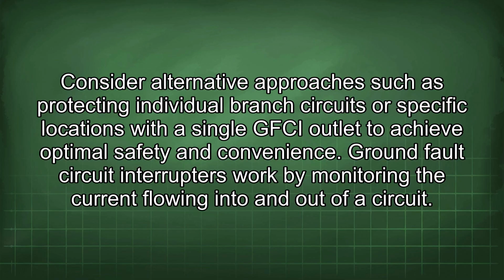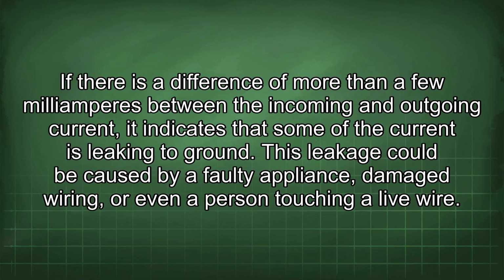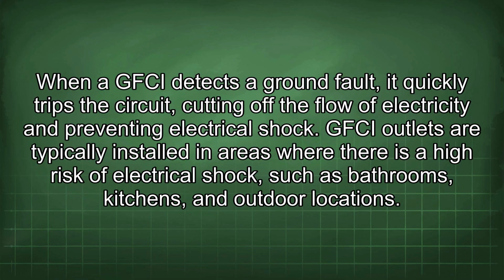Ground fault circuit interrupters work by monitoring the current flowing into and out of a circuit. If there is a difference of more than a few milliamperes between the incoming and outgoing current, it indicates that some of the current is leaking to ground. This leakage could be caused by a faulty appliance, damaged wiring, or even a person touching a live wire. When a GFCI detects a ground fault, it quickly trips the circuit, cutting off the flow of electricity and preventing electrical shock.